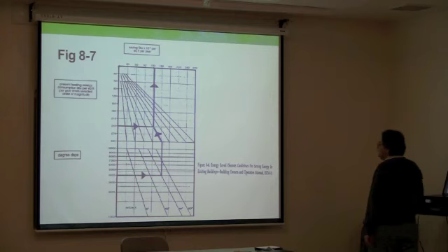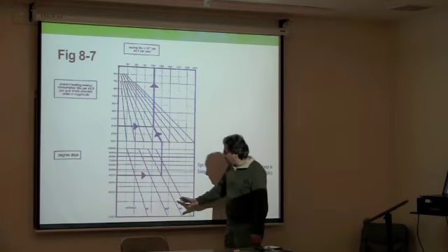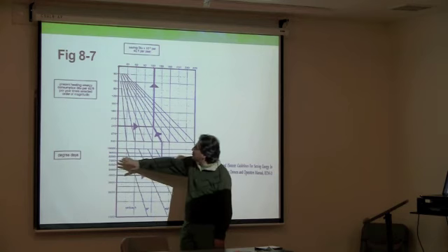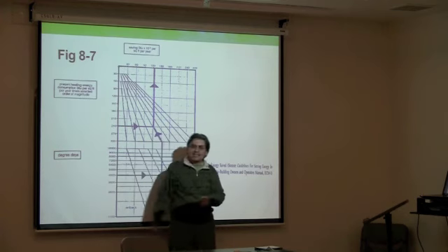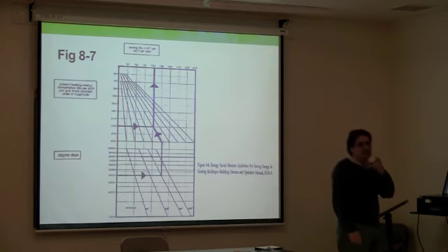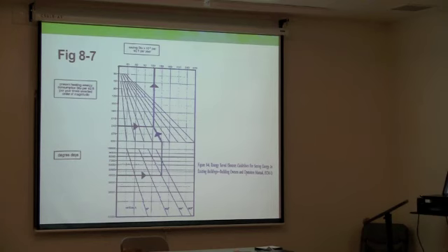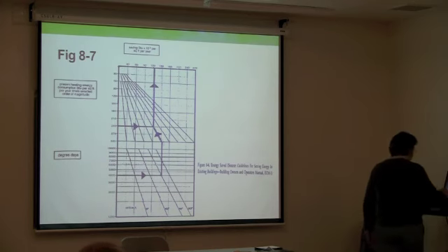So you can calculate the saving, as I said, based on how much setback you are going to have, and how many days your system is operating. One of the things you see a lot in HVAC systems is called degree days. What does it mean? Degree days is simply the number of days multiplied by the temperature difference. If inside is supposed to be 70 degrees, outside average is 80 degrees, the difference is 10. If this difference is maintained for 3 months, 90 days, I'm talking about 900 degree days, right? It's called degree days.